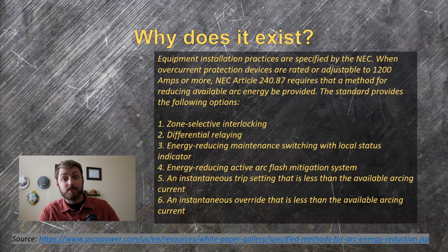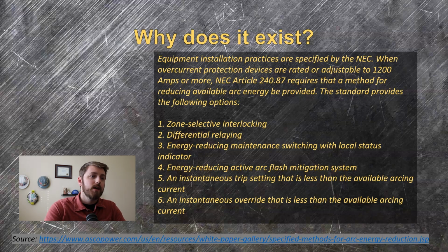Well, they exist for two main reasons. First, the law, because time has proven companies wouldn't give a shit about their employees unless they were legally required to. The NEC requires new installations of 480 volts, 1200 amps or more to be fitted with some sort of protection designed to limit arc fault energy. A maintenance mode system is just one of the options for this. I can make a whole video about all of these. Let me know down in the comments if you're interested in any of those.